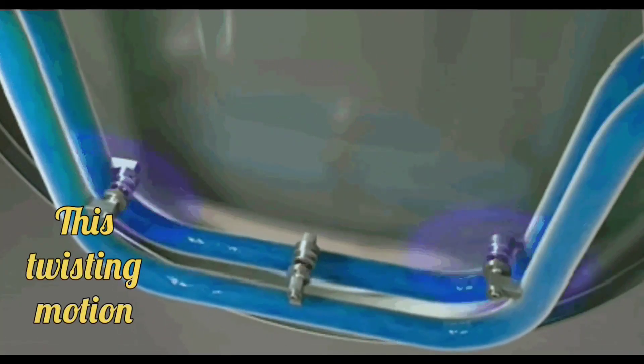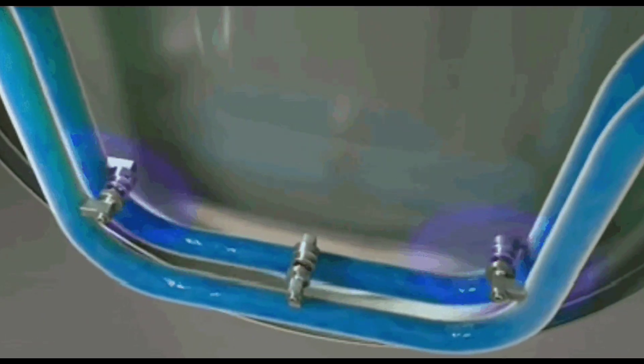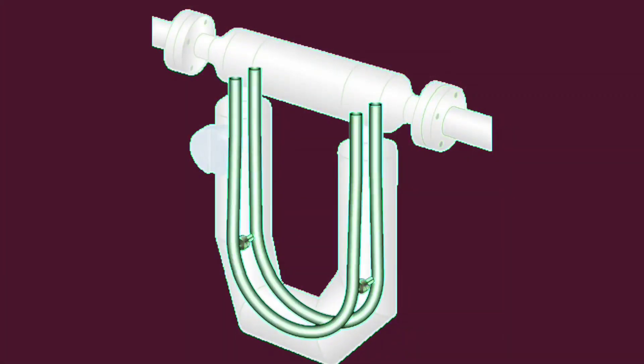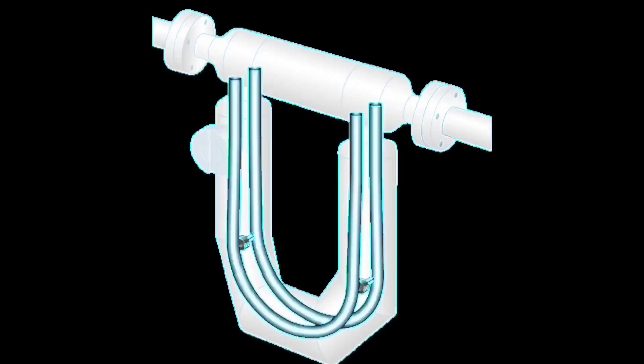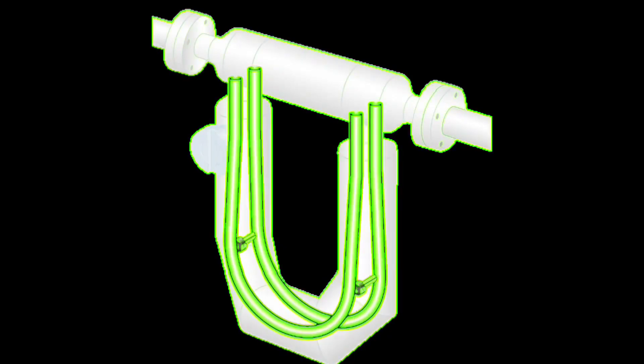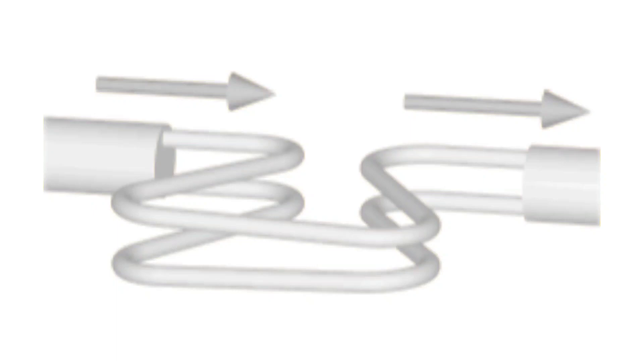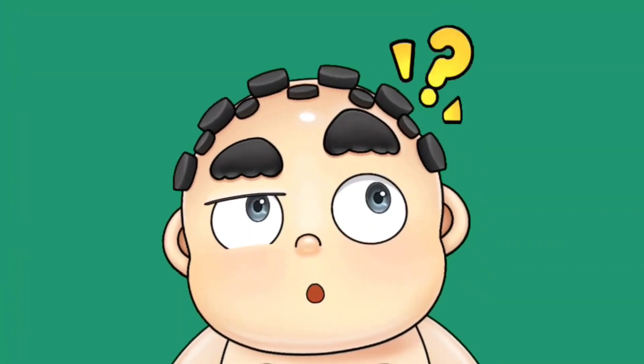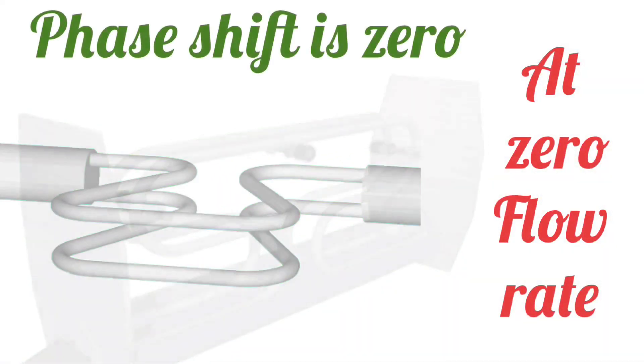This twisting motion is measured by the sensors. Due to the vibration, the tubes start to twist. The more the flow passes, the more will be the phase shift. Similarly, when there is less flow, the phase shift is reduced. At zero flow rate, the phase shift remains zero.